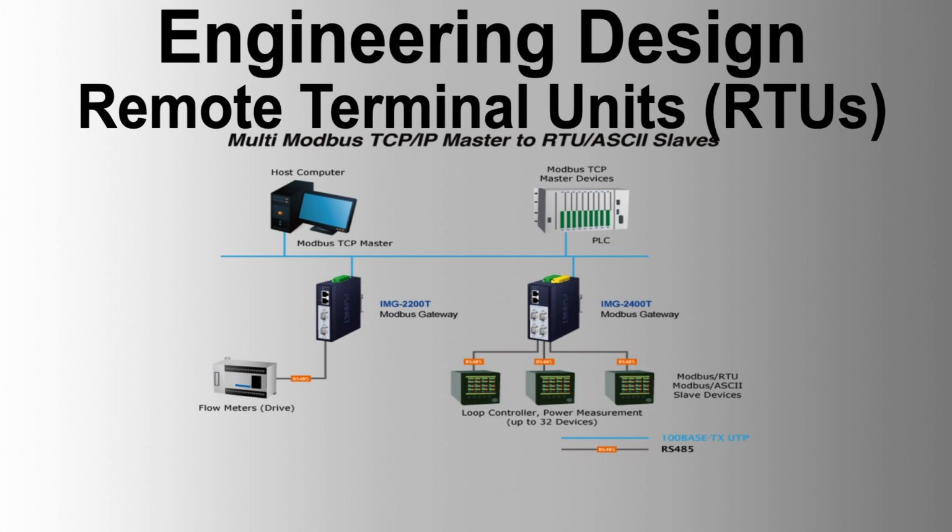Power supply and grounding: RTU power supplies accept both AC and DC inputs and are designed to support RTU operation under various conditions. They provide advanced power management, including monitoring of status and analog values, control of outputs, and LED indications for various statuses. The power supply includes inputs for AC, 90 to 260 volt AC, and DC, 20 to 60 volt DC, with outputs for load capacity, battery charging, and auxiliary power.